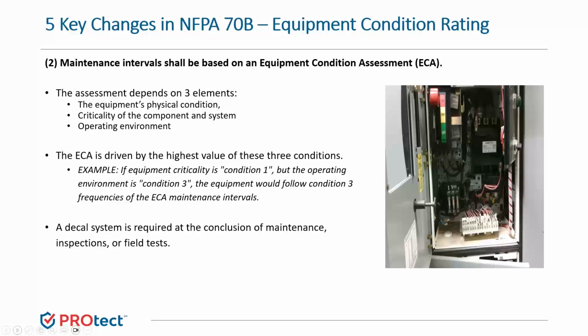So the second key change that we'll cover is equipment condition assessments. The maintenance intervals we just discussed are based on an equipment condition assessment. This assessment has several stages. It's an ongoing assessment and requires documentation, continuous review, and training to make sure that this assessment stays up to date. The equipment condition assessment process includes assessing 3 conditions for each electrical component. These 3 conditions are the equipment's physical condition, the criticality, and that can be the downline assets or processes that are not defined in that determination. And the third is the operating environment of that component.